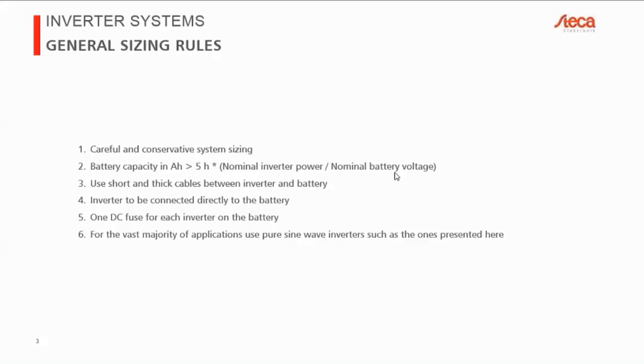So this is significantly lower than our 5 times rule here. So this is our recommendation. And then the absolute minimum, for example, for the SOLARIX PLI is 200 amp hours at 24 volt for the smaller one, 48 volt for the larger one. But we'll see those models in a moment.